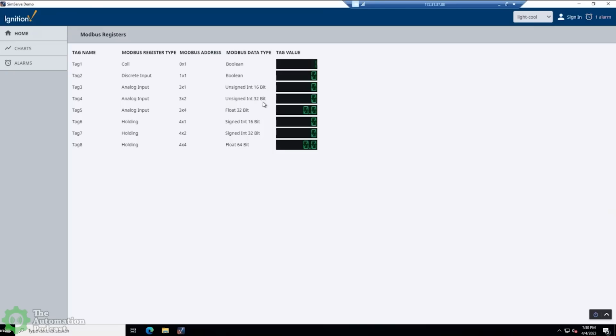The thing that's unique about this 32-bit piece here is a Modbus register is only 16 bits long. And what this one is doing, what Ignition's going to do to read a 32-bit integer is it's actually going to combine 2 Modbus registers together mathematically and calculate what that value should be. And it can be kind of a pain when you're working directly with Modbus registers to do the math on your own to figure out what value needs to be in what register to get your desired value displayed here up on the screen.